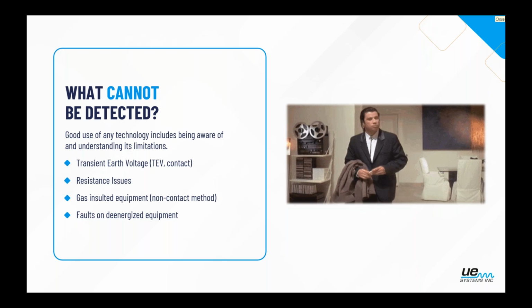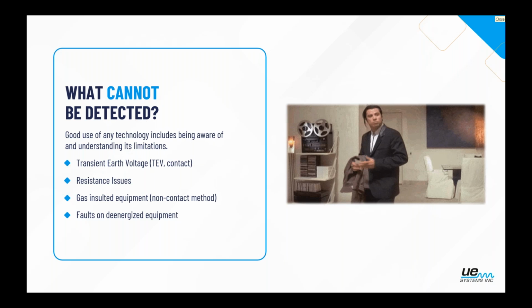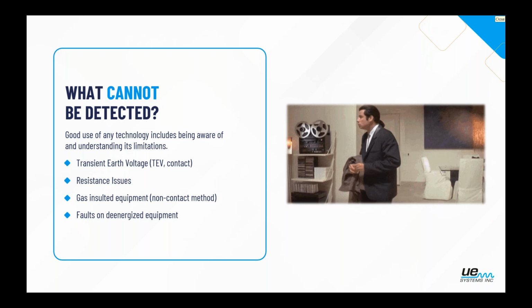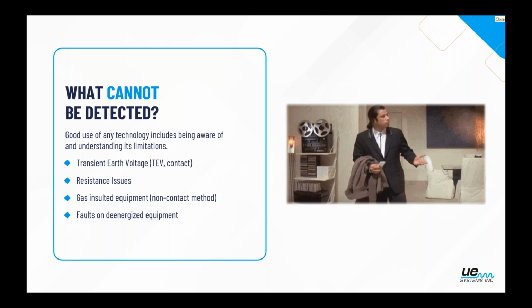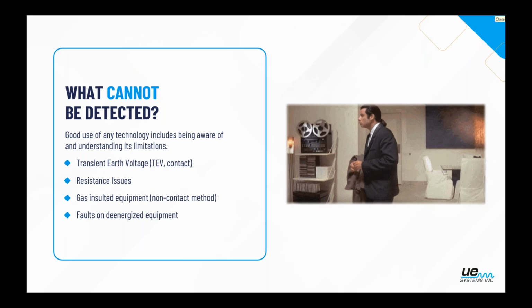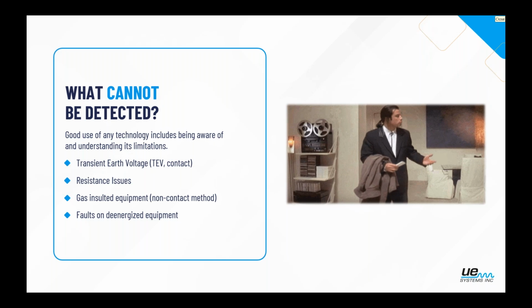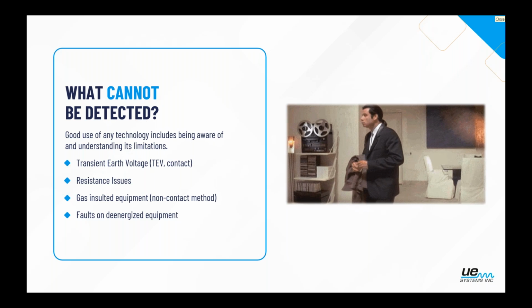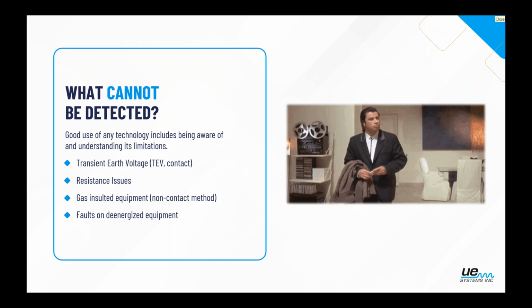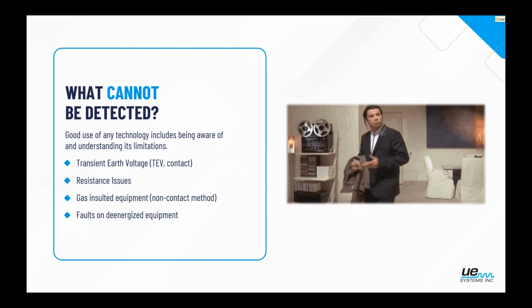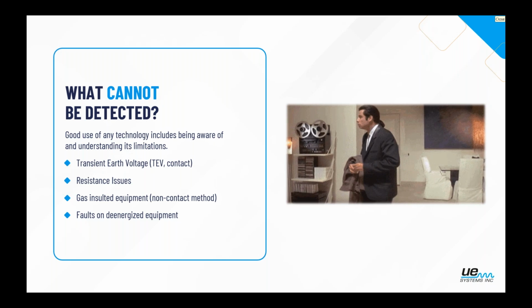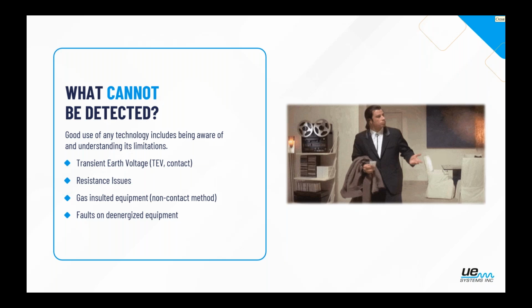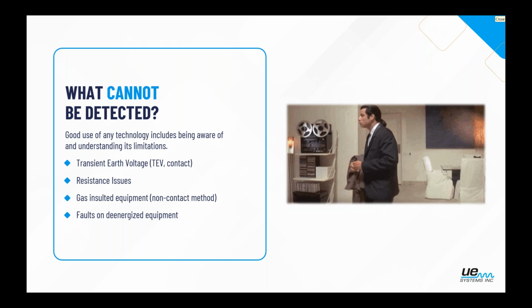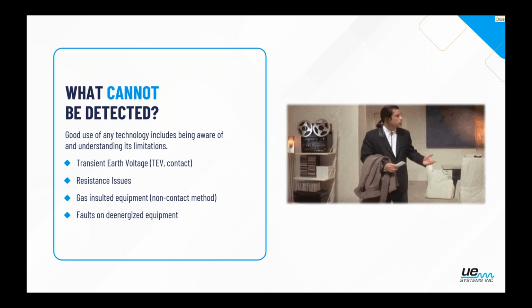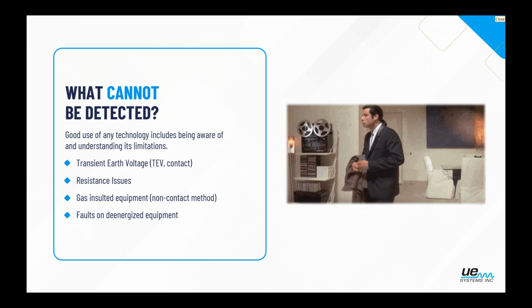And resistance issues, that's a big one. That's always going to be infrared. That's where using both together is going to give you a more holistic approach, one seeing what the other cannot, working together for the same end goal. Another thing is that we're not able to look into or listen into gas insulated equipment, just from the design of it. It is not recommended. The only way that you would be able to do it would be a contact method, which once again would eliminate what we're trying to avoid here as far as changes to safety and PPE requirements.